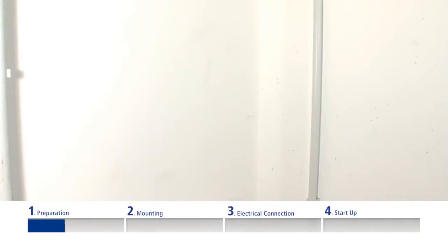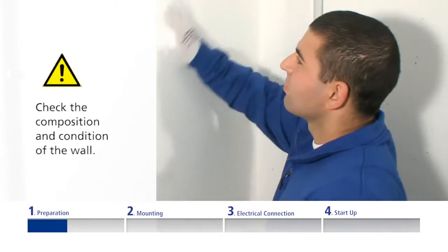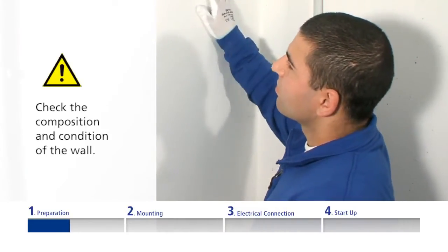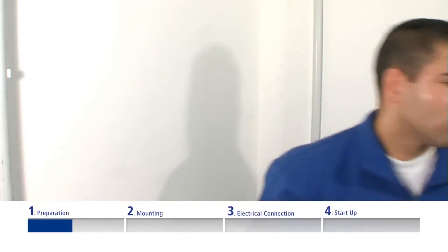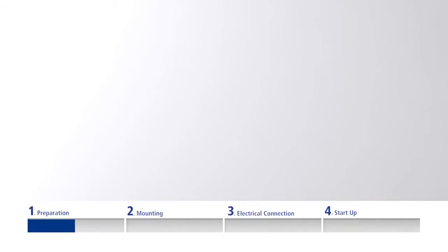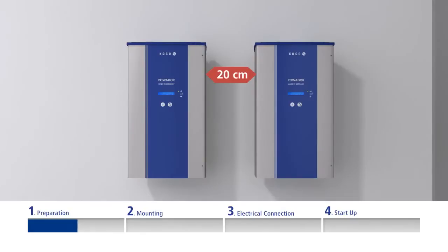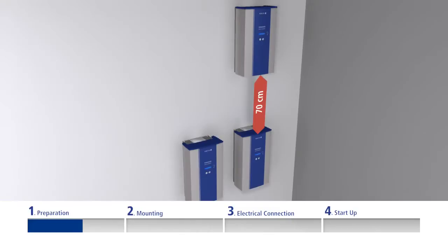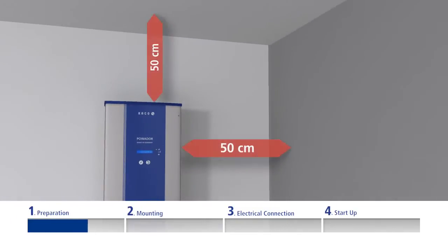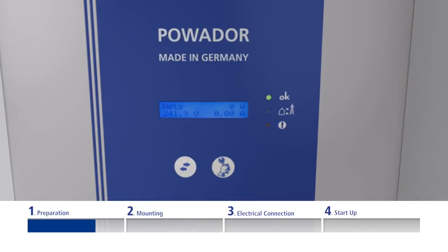When selecting an appropriate place for mounting, check the composition and condition of the wall and ensure good access to the unit. Maintain the following minimum clearances around the unit: 20 centimeters between inverters mounted side by side, 70 centimeters between inverters mounted above each other, 50 centimeters to the floor or ceiling, to shelves, cabinets, or similar. When arranging the inverters, please also ensure that the inverter displays will be clearly visible afterwards.